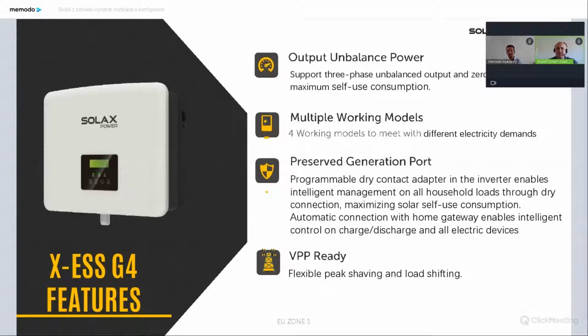I've seen in the chat there have been some questions about unbalanced output power. In on-grid, but also in off-grid mode, the inverter can output unbalanced power. Normally the power on all three phases is balanced, but with SolaX inverters you can activate an unbalance on the phases, and the maximum power on each phase is a third of the inverter power. For example, if you have a 12 kilowatt inverter, the maximum power is 4 kilowatt on each phase. If you have a 15 kilowatt inverter, the maximum power is 5 kilowatt on each phase.